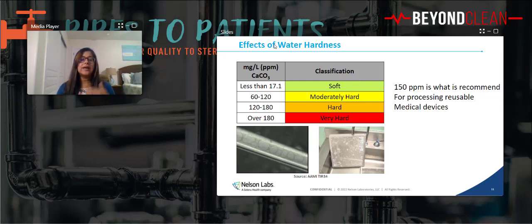Now, why do we have this scale of water? TIR34 specifies, it's a TR, it will be a standard, and it's still the same thing, 150 ppm is what's recommended for processing reusable medical devices, right? And where's 150 ppm? It's between hard, but most of the time, depending on the season, you will see that we're over 180. And soft water is what your critical system should be at, right? That is what you want. You want soft water for critical systems.